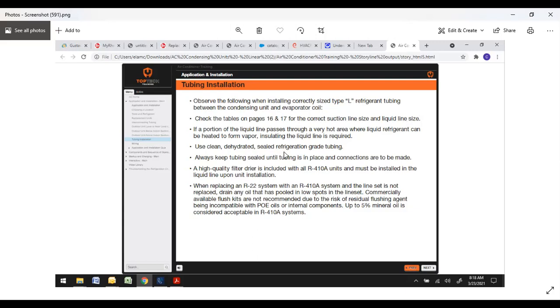Always use clean, dehydrated, sealed refrigeration grade tubing. Don't take your ends off until you're ready to make your connections. Always keep your tubing sealed until it's in place and connections are ready to be made. Used to see guys all the time, they'd pop the caps off and then they'd start running their line sets. Once you get debris in there, unless you take time to blow it out, which they never do, you'll end up with stuff that'll end up blocking your piston. It'll end up fouling up your TXV, your filter dryer.